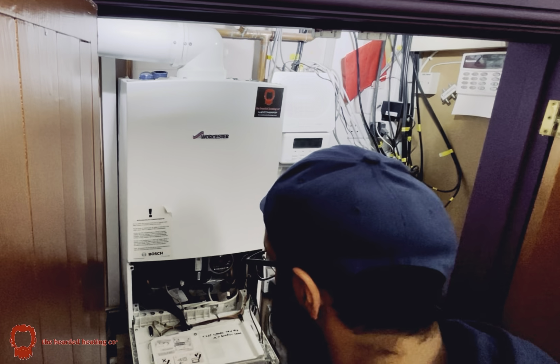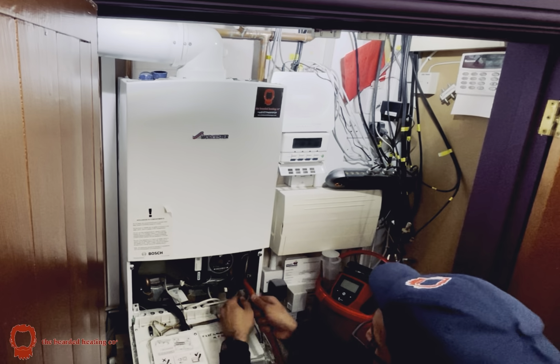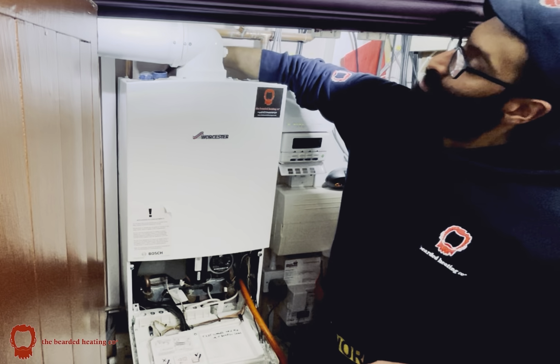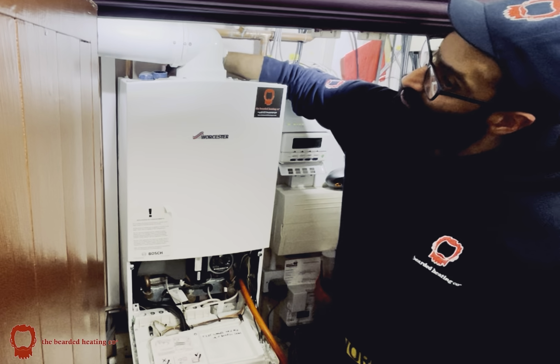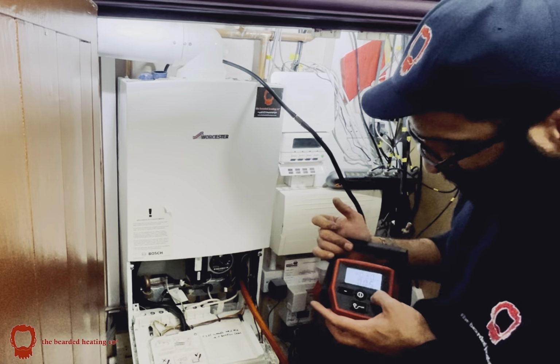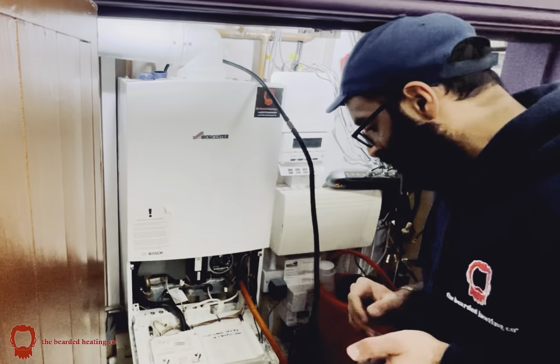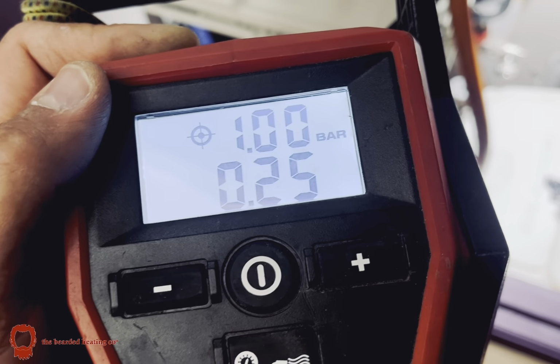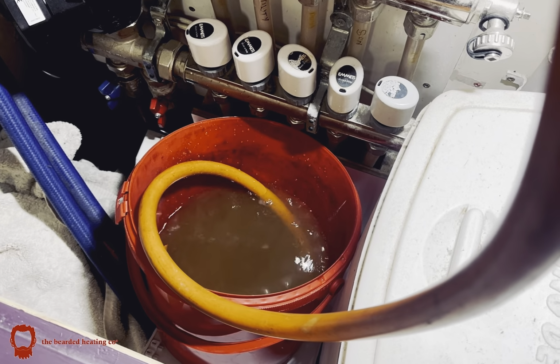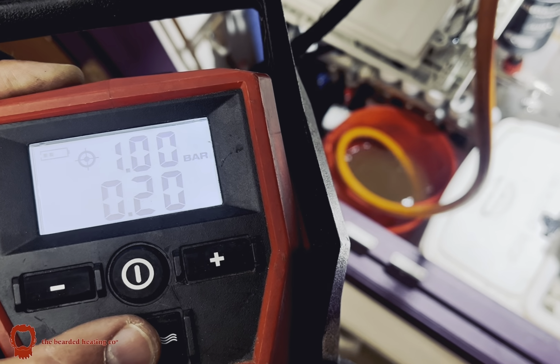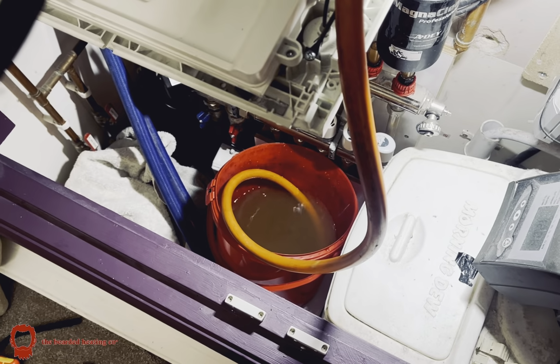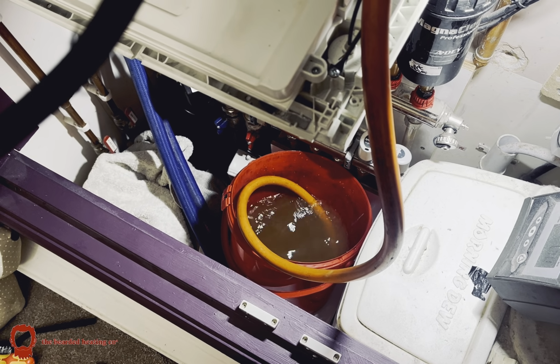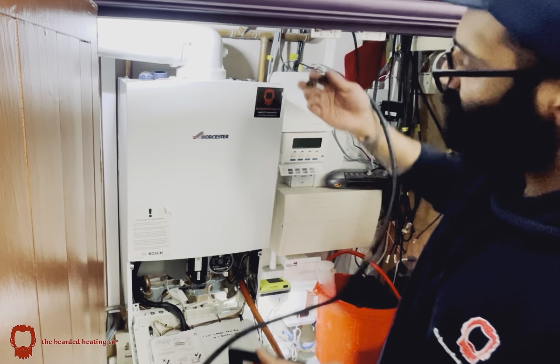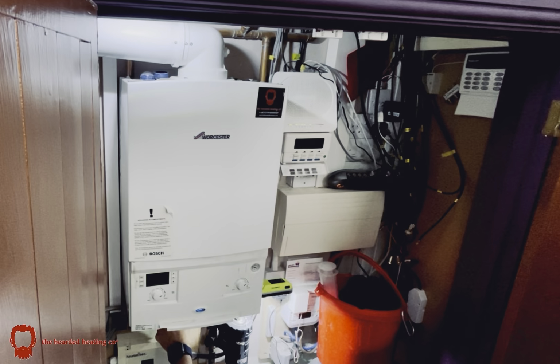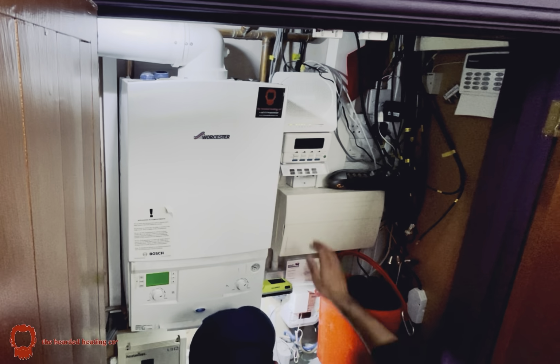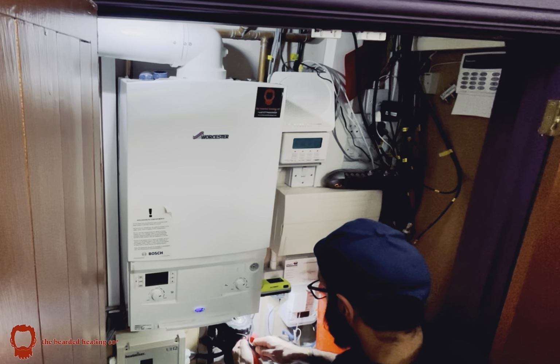And now I thought, oh yes, let's check the expansion vessel to make sure that's all good as well. So I drained the water out of the boiler, and I went to recharge the expansion vessel using my Milwaukee air compressor. And noticed, as you'll see, that it's pumping, but the bucket is just gurgling with air no matter what I did, and that is because the expansion vessel itself is ruptured. So that's just the air coming from the compressor back through the hose. So I told the customer that I'm going to have to come back with a new expansion vessel. So I'll return again and take this boiler off the wall and replace the expansion vessel behind it.